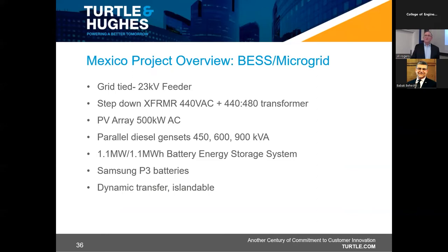So one of the tests we did, they were having problems with the grid power being intermittent and poor quality. So we installed the battery system. We actually cut the power. We went out to the main breaker, cut the power where the feeder comes in from the utility, and the factory stayed running on batteries.